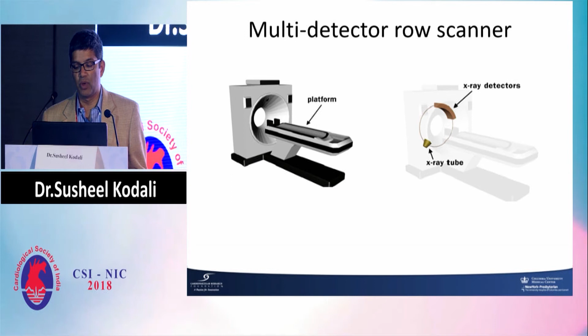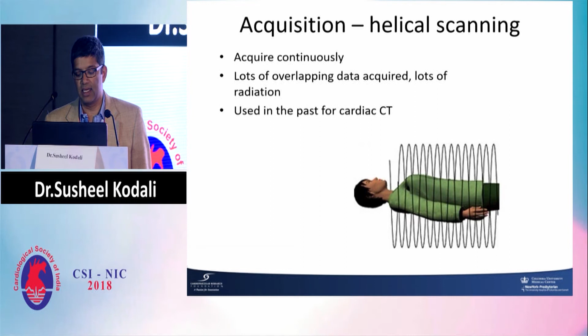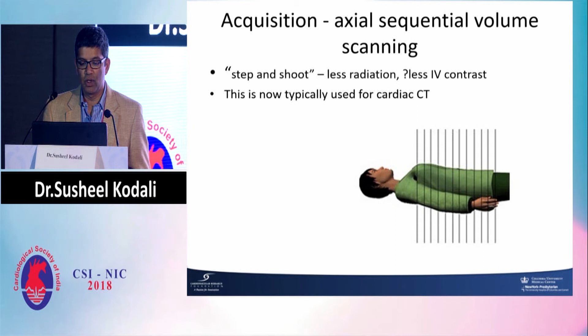And in the past, this was used for cardiac CT. But it's lots of data, lots of radiation, and lots of overlapping data, unnecessary radiation. So generally for cardiac CT, we don't do helical scanning for the most part. And most of it now is axial. So with an axial scan, you get one scan, then the X-ray tube's off, the scanner moves, then it gets the next. You need to step as much as you need to get the entire field. So if you're doing the entire thorax, you're going to step multiple times. This is what we use for cardiac CT.